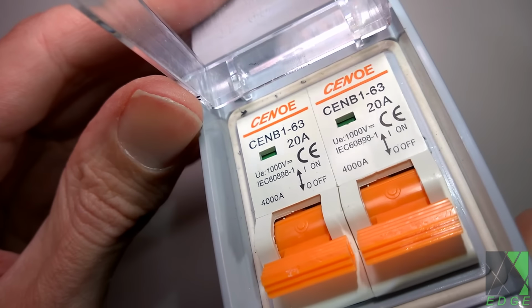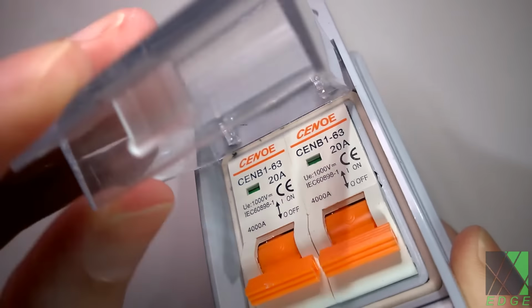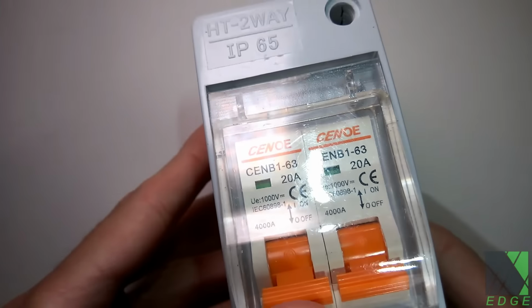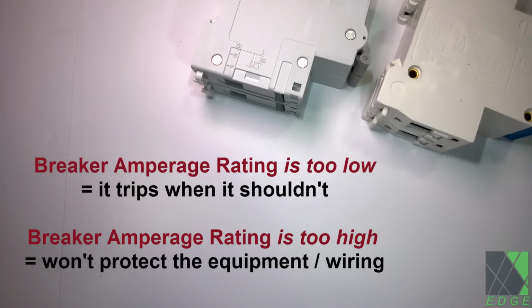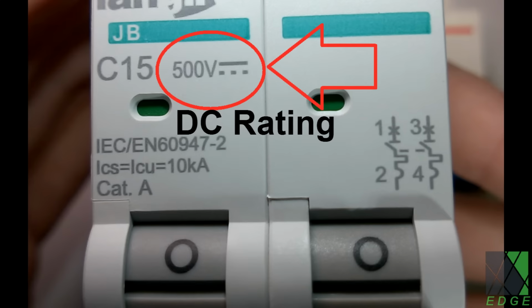It is important to pick a breaker with the right amperage rating for the application. Too low and the breaker will activate when there is a surge draw under normal operating conditions, for example, when an inverter starts up an air conditioner. Too high and it won't activate when there is a short circuit or a fault, leading to damage and possibly a fire. It's a good idea to learn to read and understand the labels on the front of the circuit breaker. For example, being able to tell the difference between AC and DC markings.